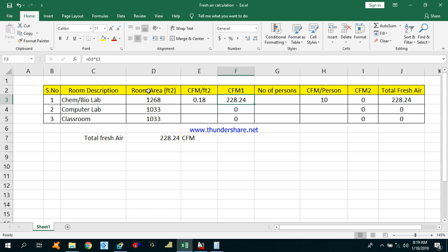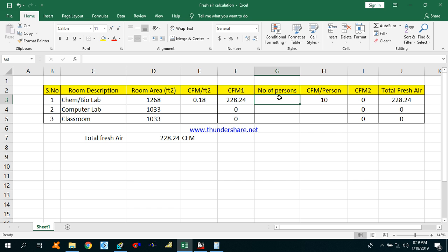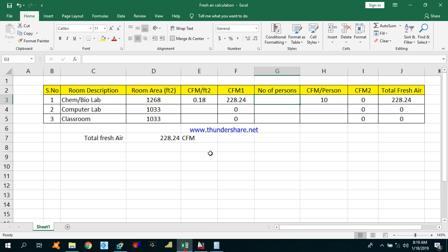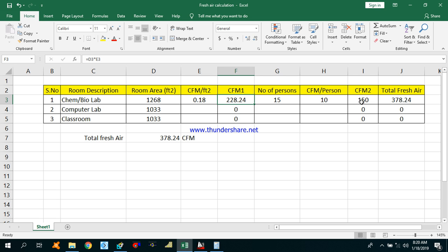Using the formula already applied in the Excel sheet: room area multiplied by CFM per square feet gives CFM1, which is 228. Assuming 15 persons in the chemistry bio lab, CFM2 is 15 times 10, which is 150. The total CFM for the chemistry and bio lab is CFM1 plus CFM2, that is 228 plus 150, which equals 378 CFM.